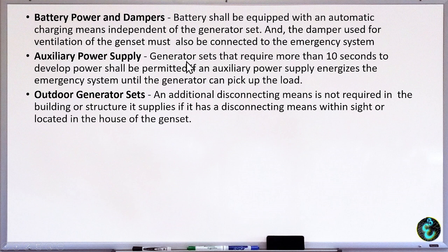Auxiliary power supply, generator sets that require more than 10 seconds to develop power shall be permitted if an auxiliary power supply energizes the emergency system until generator can pick up the load. So this is commonly used in healthcare facilities. Aside from having a generator, they also have what we call a battery bank, so while our generator is picking up the voltage, what carries the load is the battery bank.